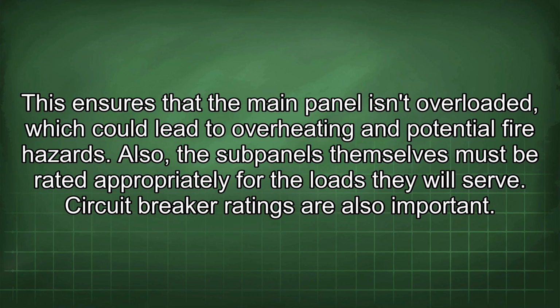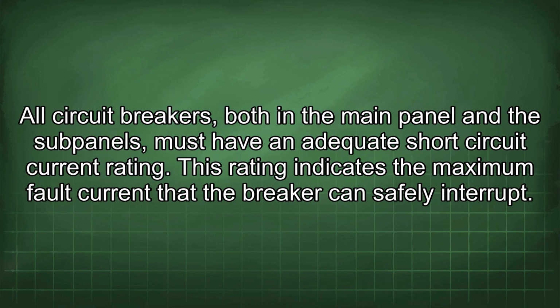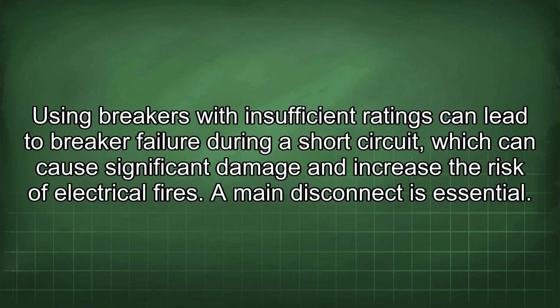Circuit breaker ratings are also important. All circuit breakers, both in the main panel and the subpanels, must have an adequate short circuit current rating. This rating indicates the maximum fault current that the breaker can safely interrupt. Using breakers with insufficient ratings can lead to breaker failure during a short circuit, which can cause significant damage and increase the risk of electrical fires.